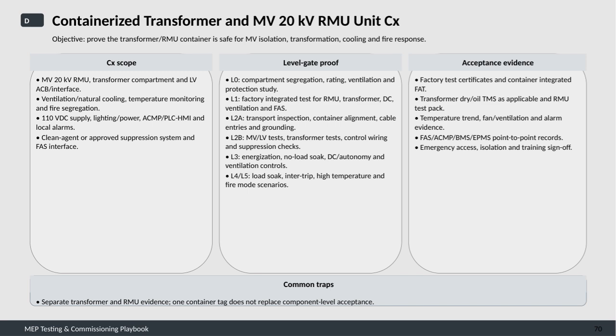Transformer tests such as dry or oil temperature monitoring systems and RMU test packages are critical. Continuous temperature trend monitoring, fan and ventilation operation evidence, and alarm records are necessary. Additionally, records from the fire alarm system, air circuit breaker management platform, building management system, and emergency power management system must be documented. Emergency access procedures, isolation protocols, and training sign-offs complete the acceptance criteria.